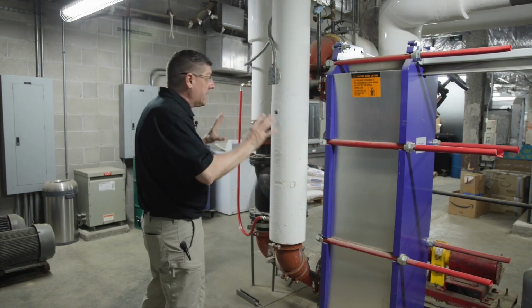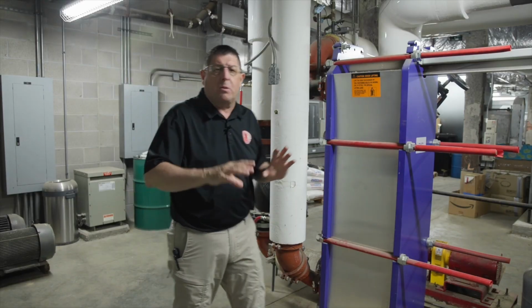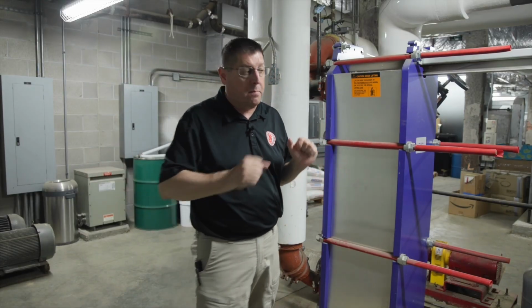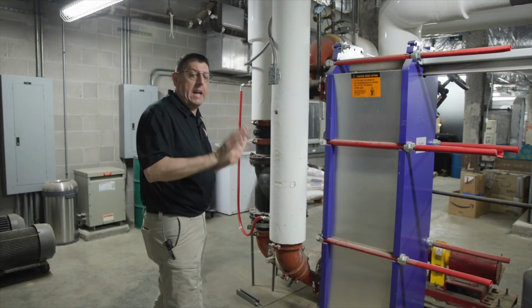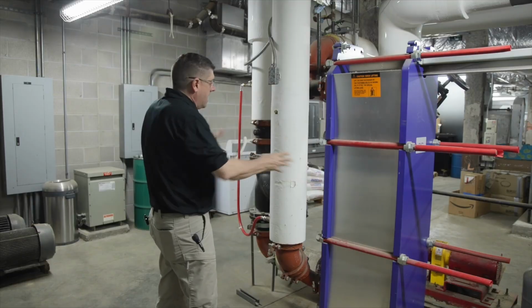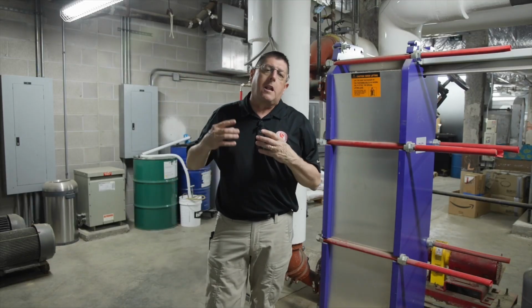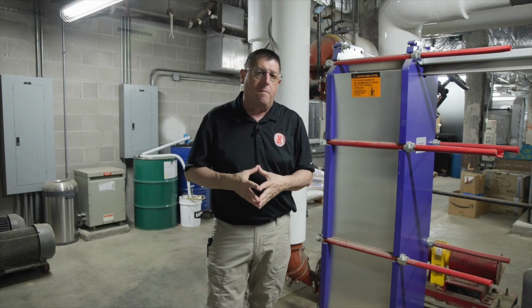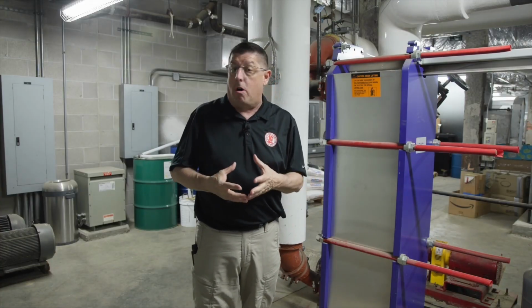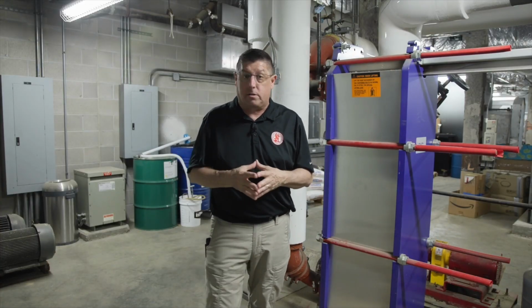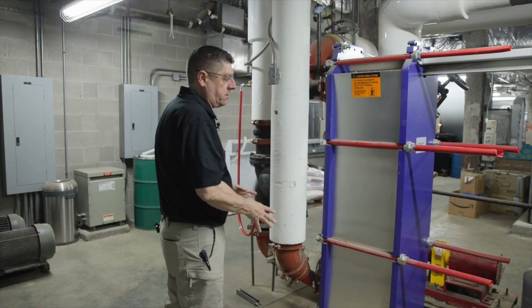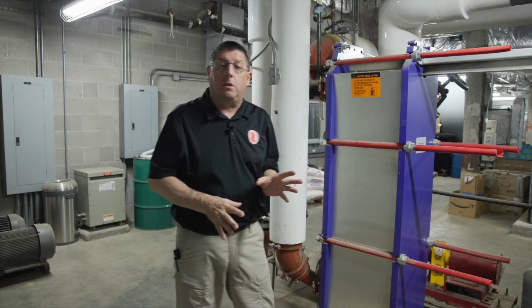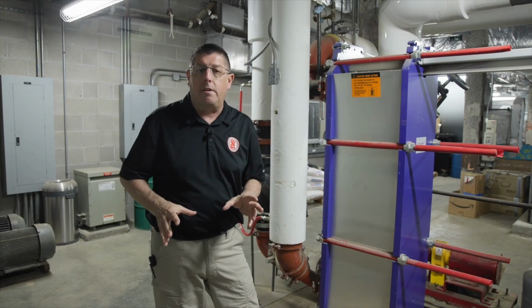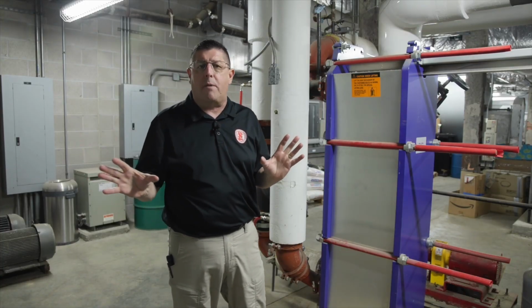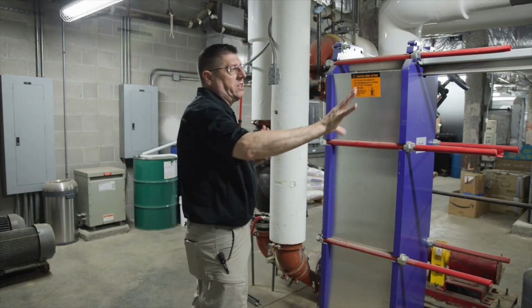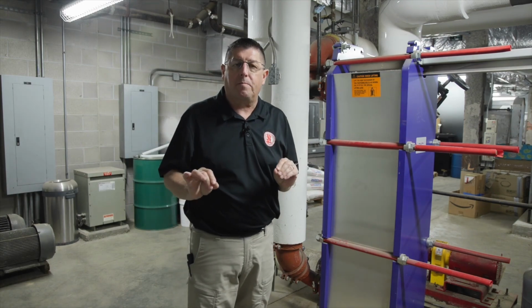And so to protect this system, not to protect the building, but it does protect the building, but to protect this system, a secondary assembly has been placed here where instead of using the water from the chiller, it's actually got glycol or an antifreeze type product flowing through these pipes. And all that does is help prevent, in the event of the catastrophic emergency, this system from freezing up.